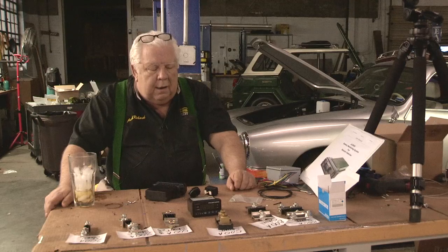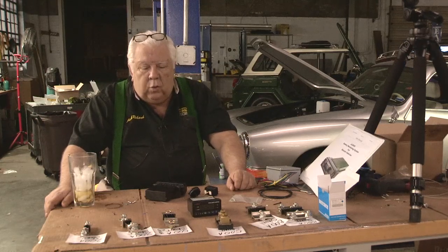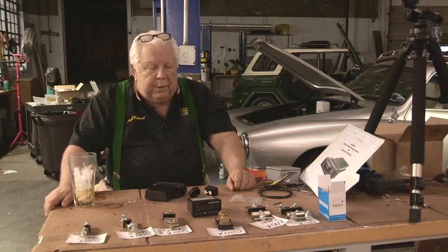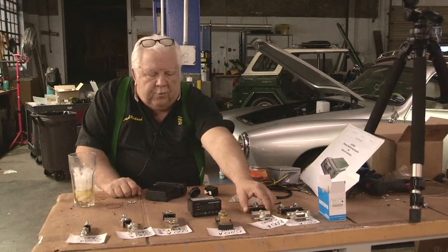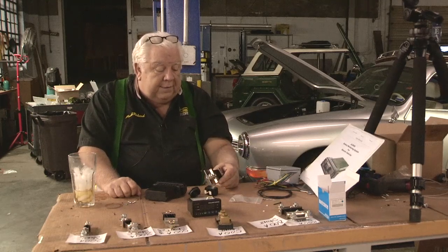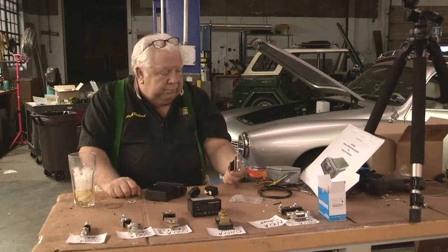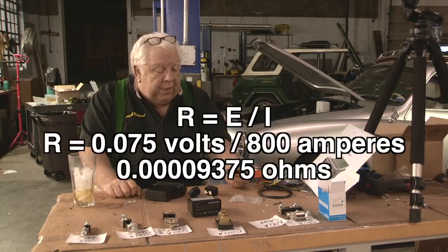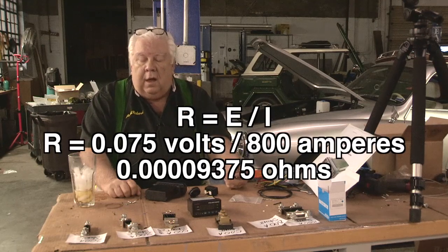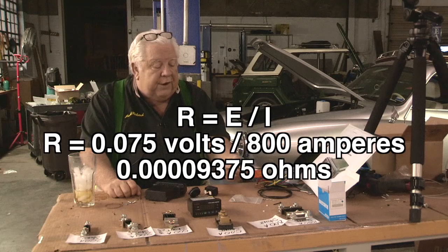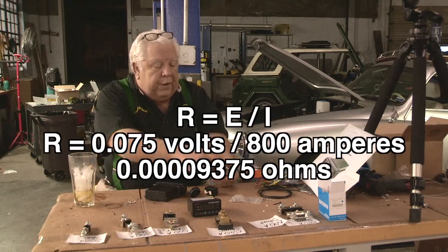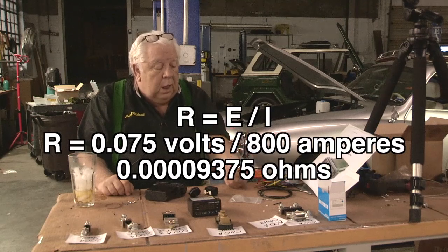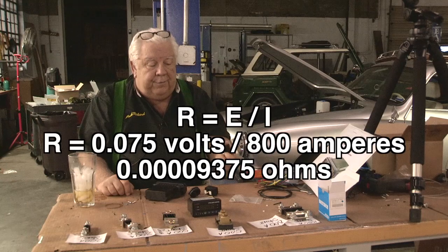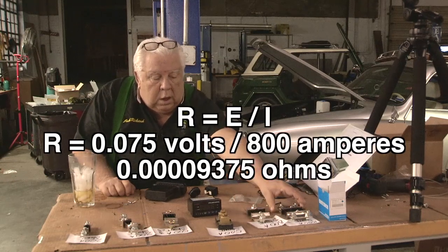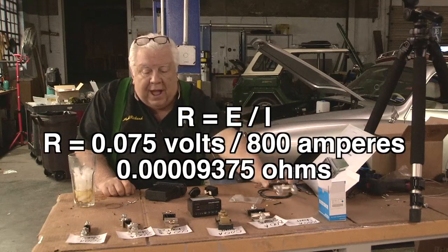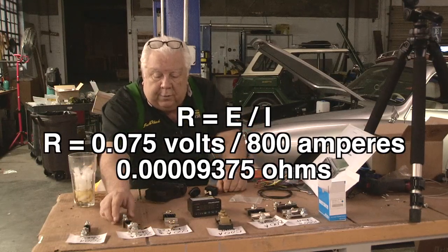They tend to be rated in three ways, and two of them you're familiar with. And we're going to talk today a little bit about the third. This is an 800 amp shunt, 75 millivolts. And what that means is that the resistance of this is such that you will read 75 millivolts from one of these little terminals to the next across the shunt part at 800 amps.